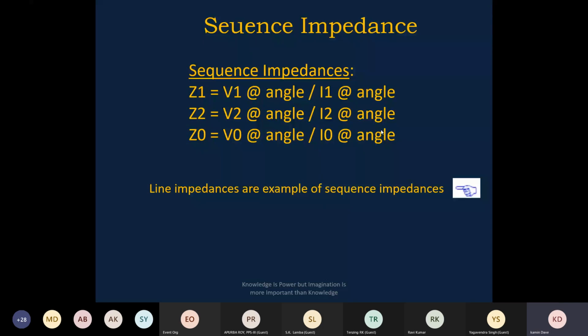Z1 is equal to V1 magnitude at angle divided by I1 magnitude at angle. So that is called positive sequence impedance. Similarly, the negative sequence impedance and zero sequence impedance. Normally, when we do the line relay settings, we always ask for the impedance parameters. Let us say 0.5 plus 1.5 ohms, so R plus jX. That is called the positive sequence parameter of the line, the Z1 setting. That is the Z1 parameter.